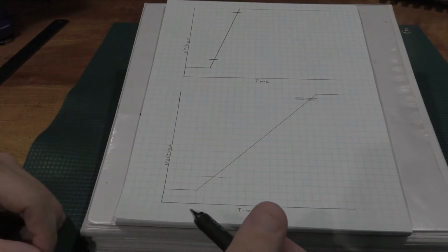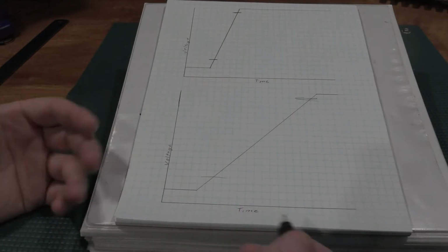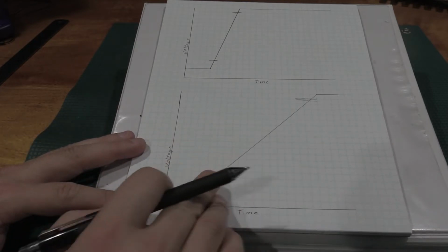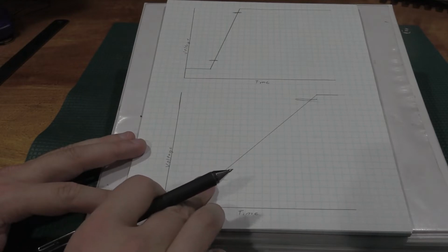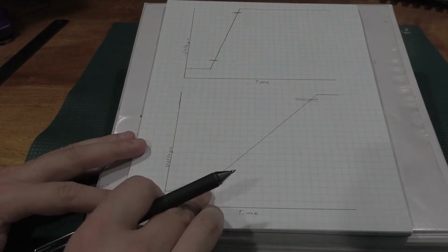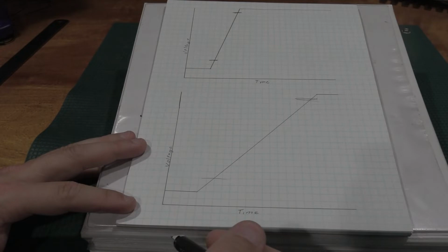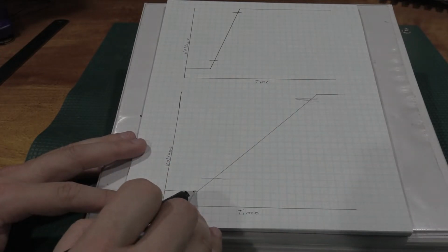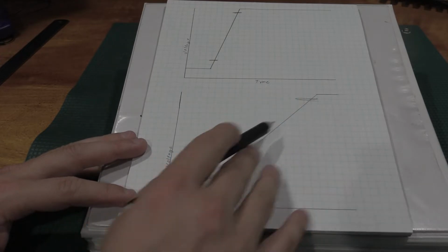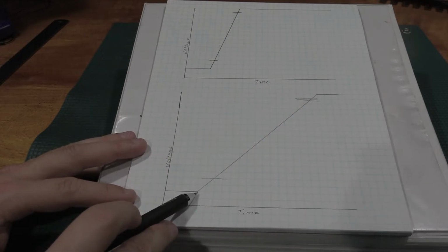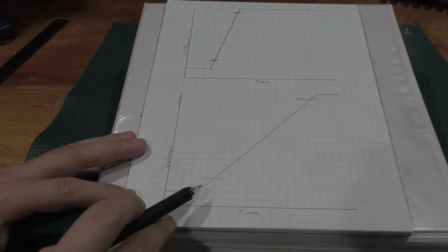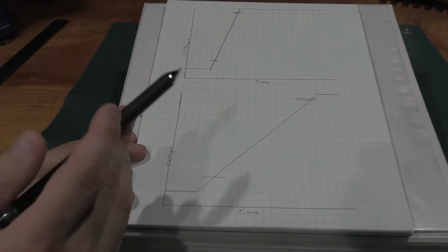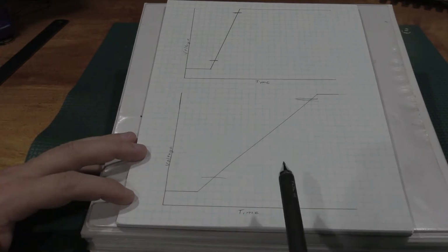A lot of the function generators that I've seen people try to use to align and calibrate scopes don't have a steep enough edge, and that's the problem. When you're doing the high frequency calibration of an oscilloscope, this edge should be as clean as possible. It should be as steep as possible. So this would be a very poor square wave. This one would be better for aligning the high frequency chain of a scope.